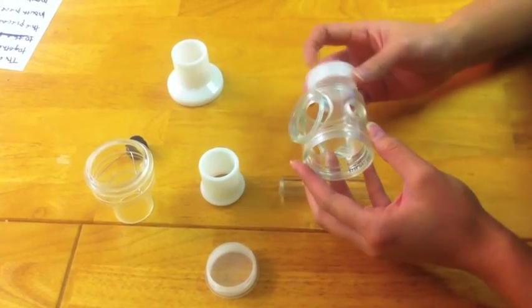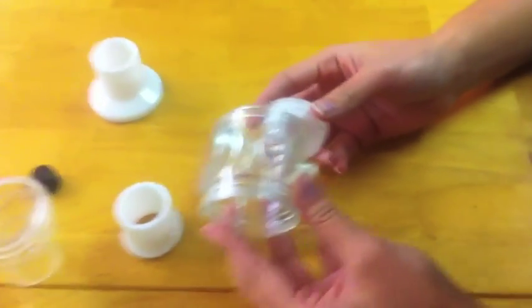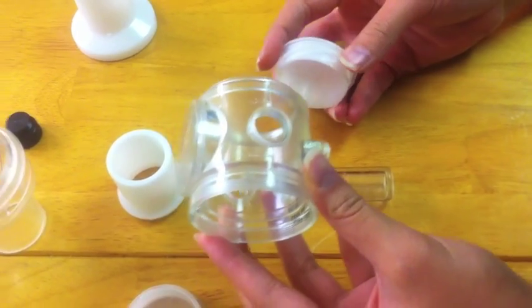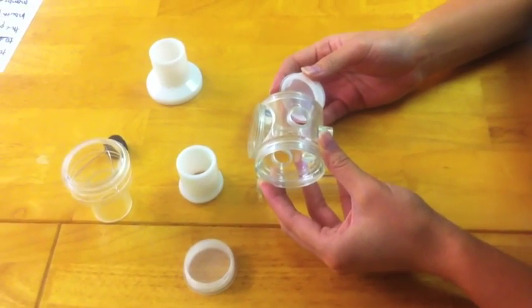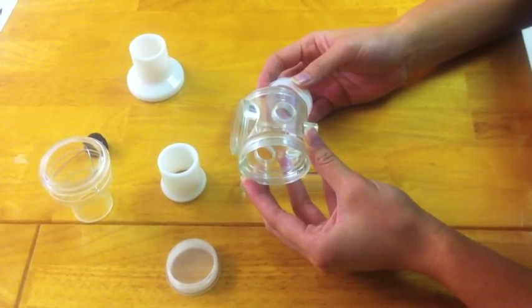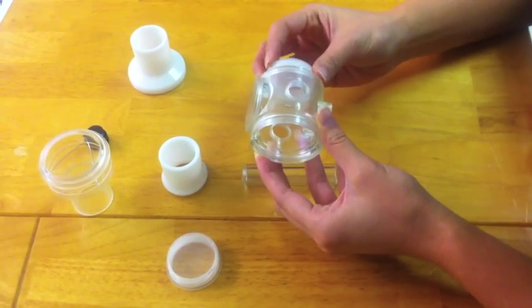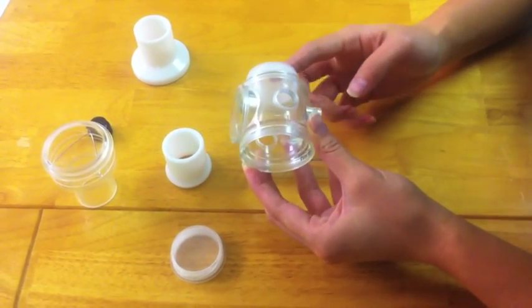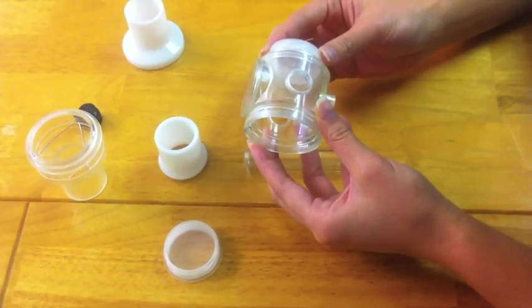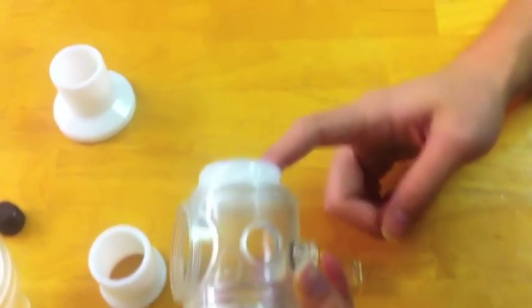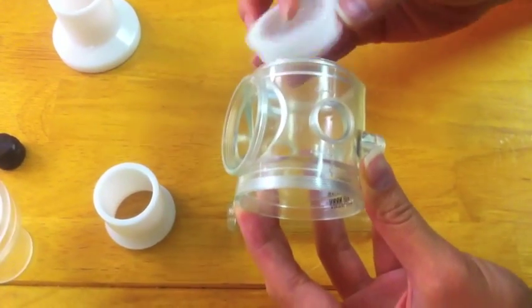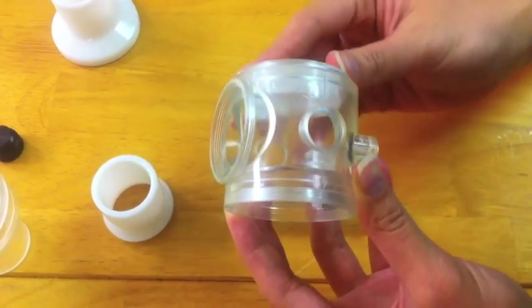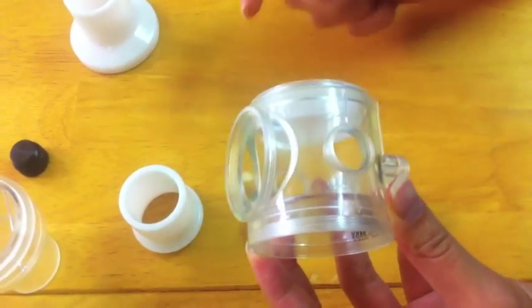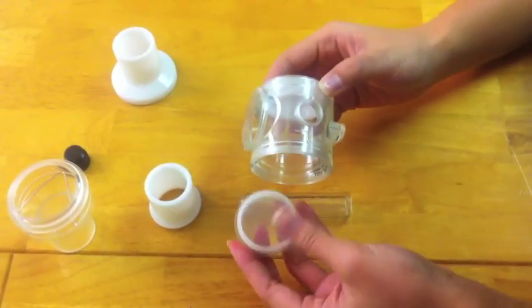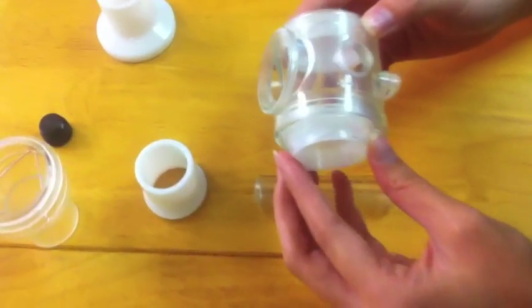As you can see, on top of the body there are arrows indicating in which way air will be flowing. The way in which air goes in depends on which way the membrane faces. If you place a membrane facing this way, the air will not be able to enter, causing an error. So you want to face it the other side, according to the arrow. And both of them need to be facing the same direction.